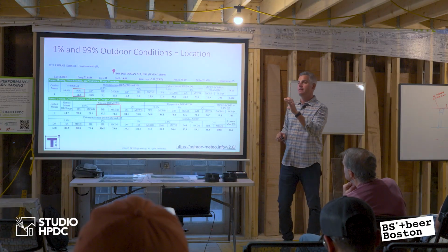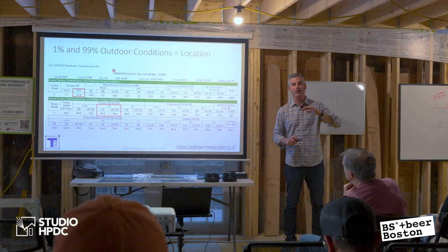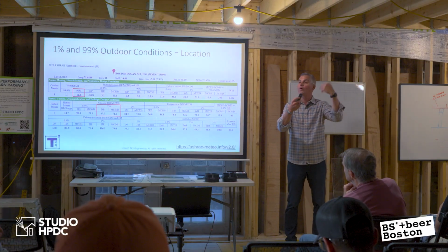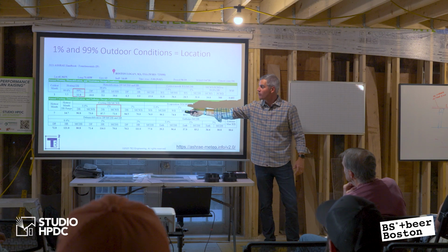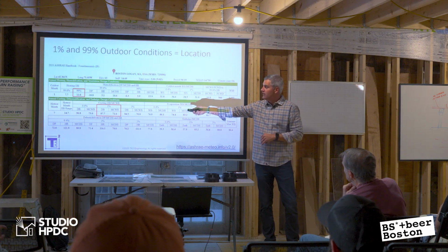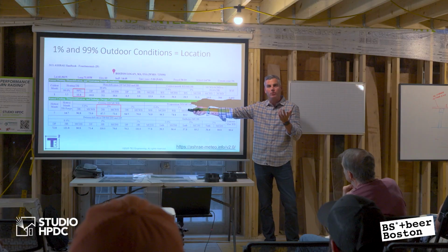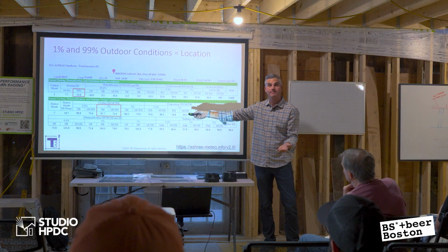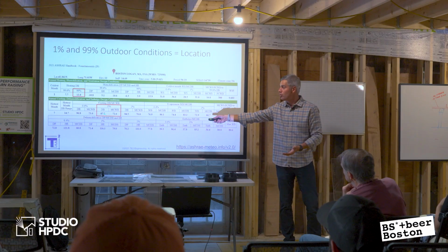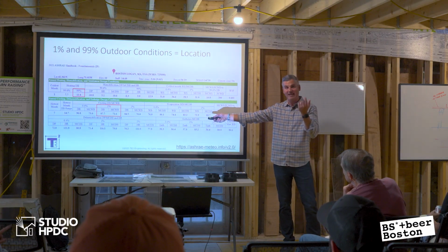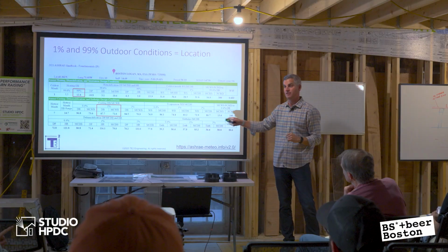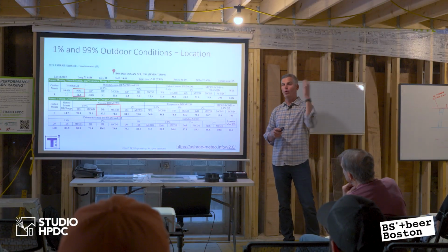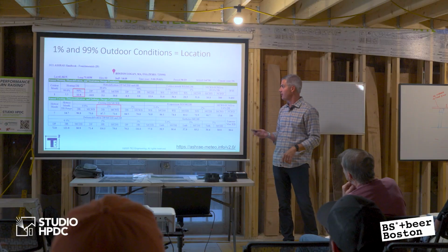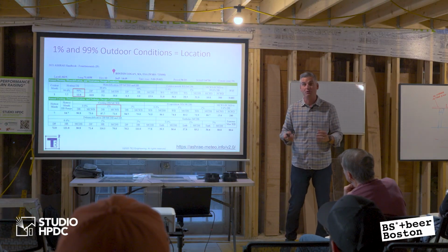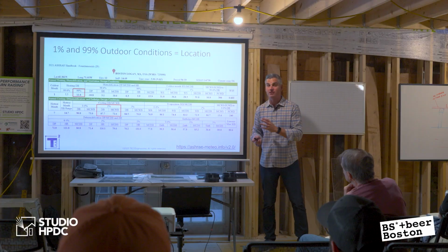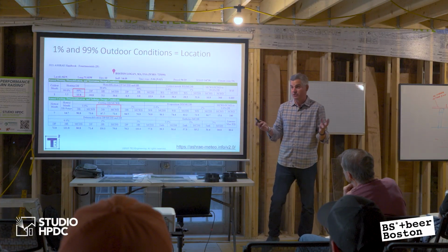What these mean is that 99% of the year, the temperature outside is either warmer or colder than these temperatures. So in the example of 12.8 degrees in Boston at Logan, 1% of the year, basically 87 hours a year, the temperature might be lower than that. And the same thing on the other side, cooling, 87.7: there's going to be 1% of the year, about 87 hours, that the temperature could be above that. A very common question I get is that we're always 95 here. People think that. But the reality is we're not at 95 degrees all that often, right? That's just the reality of it.